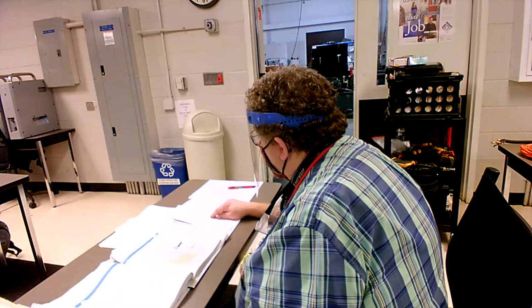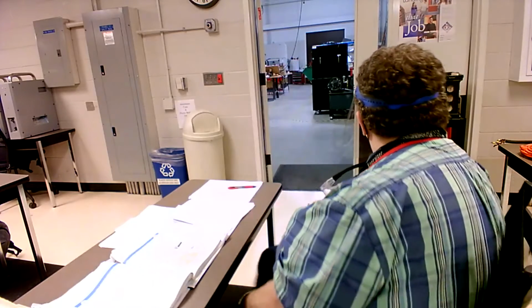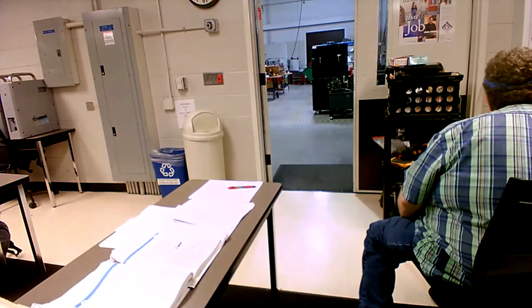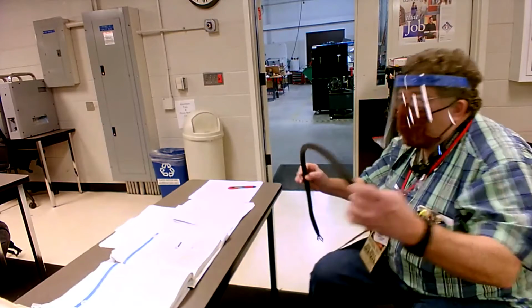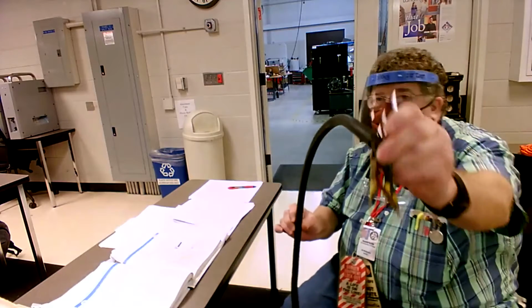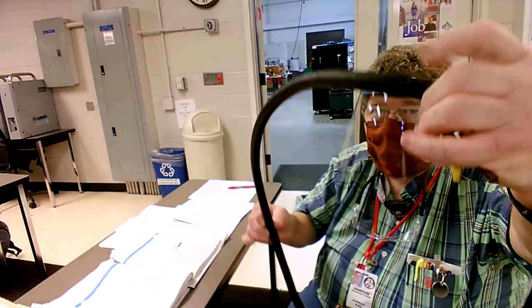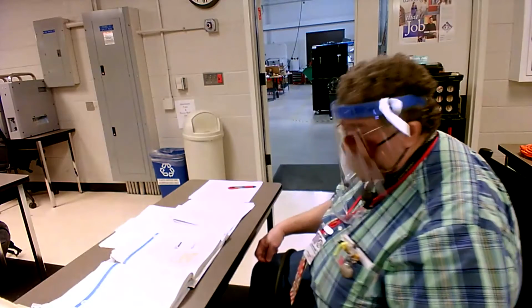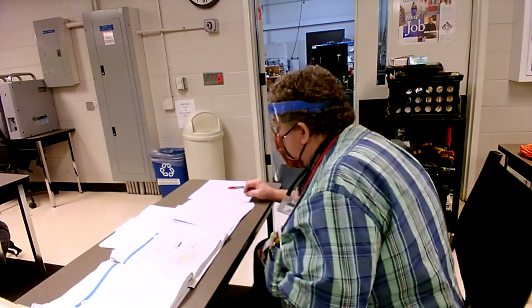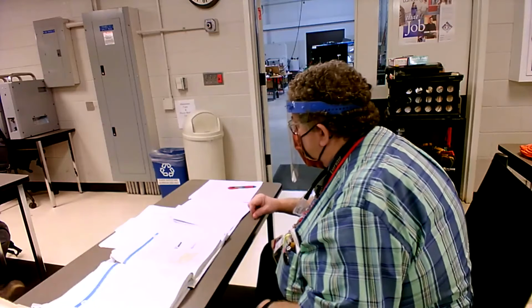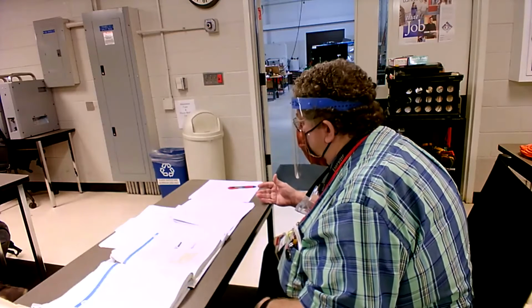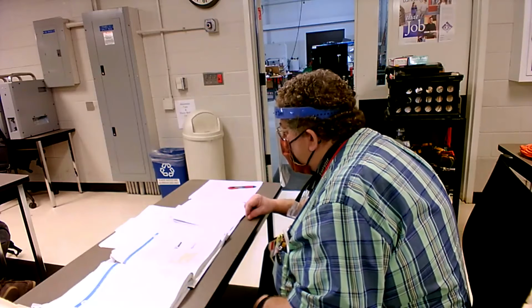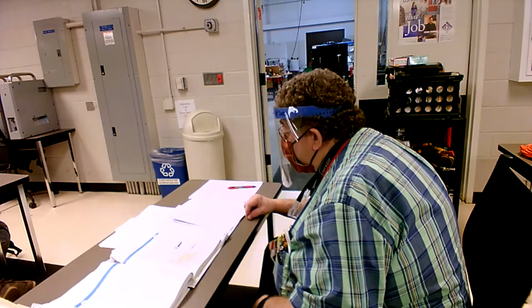The question is the kind of insulation, and the insulation is the coating. The coating on that wire is like a thermoplastic type, some type of jacket on there. That's what we're talking about, the insulation that goes around the actual copper wire. The kind of insulation on the conductor partially determines the conductor's current carrying capacity.